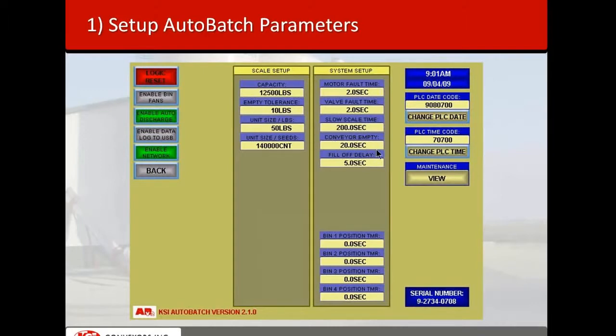The conveyor empty time is the amount of time we give the conveyors when we're filling the scale and the conveyors go into cleanout mode, how many seconds we let those conveyors run. For example, if we're running seed from bin number 3 and the bin gate closes, we let those conveyors run for 20 more seconds, and after that 20 seconds, we assume that those conveyors are cleaned out and empty. The fill-off delay is just a way to add time to this 20 seconds. Typically, this is 0 seconds on your system.